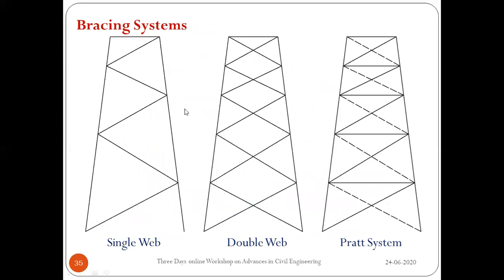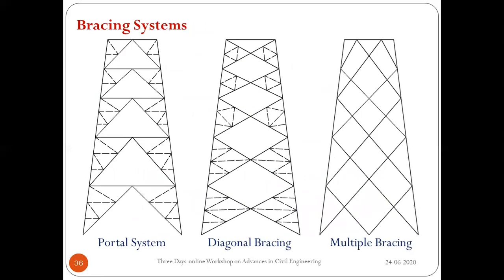Bracing types vary depending on tower size: single web, double web, Pratt system, portal system, diagonal bracing, multiple bracing, or combinations. In the field, a combination of inverted-K (portal system) and diagonal system is commonly used — inverted-K at the bottom two or three panels and diagonal above. Dotted lines represent redundant members, which help reduce the effective length of main members such as legs, bracings, or belts.